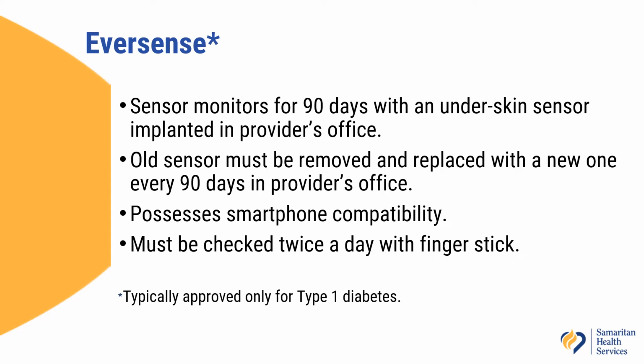This one is a sensor that is replaced every 90 days, but is replaced in a provider's office because it is surgically implanted underneath the skin. So every 90 days you have to come get a little incision, have that sensor removed, and a new one replaced. This also possesses smartphone compatibility. This one does have to be calibrated with a finger stick, so you do have to do a traditional finger stick twice a day in order to calibrate this sensor. It is typically approved only for type 1 diabetics.